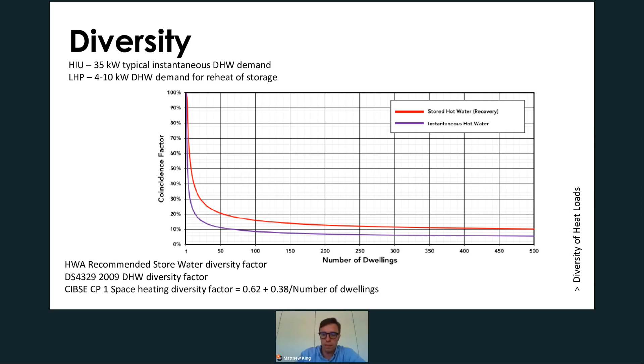The other element is waste heat. The fifth generation network has a great opportunity to utilize very low temperature energy sources, and there are a lot of them in an urban environment - data centers and other environments are an example. The fourth generation obviously has a higher grade energy center and distribution, but with suitably designed water to water heat pumps can utilize these sources too, though they require higher supplementary energy input because they have a lower COP when doing that. So I'd say fourth generations are slightly better suited to heat pump technology, but looking at it overall, and as in previous presentations, it's very project specific.